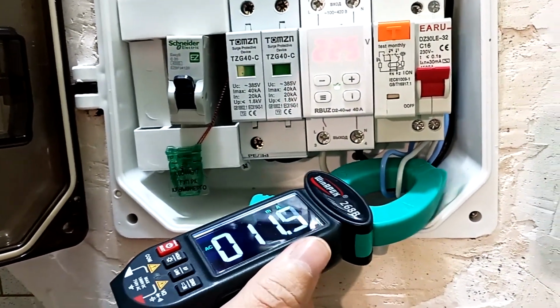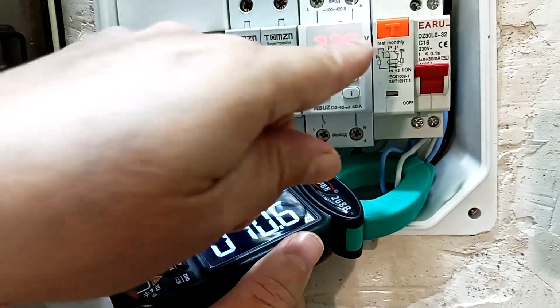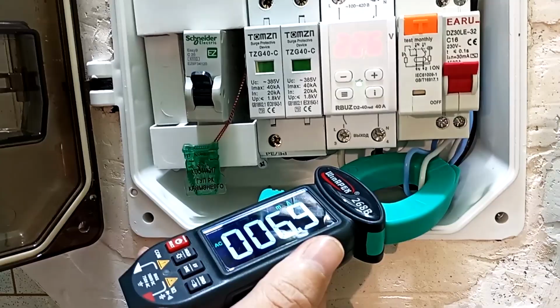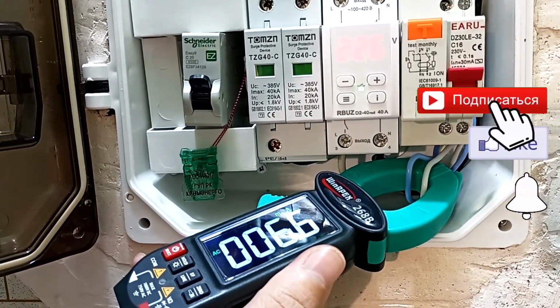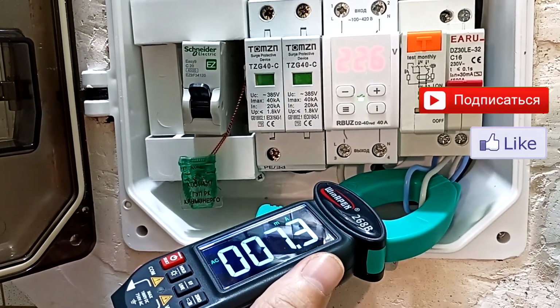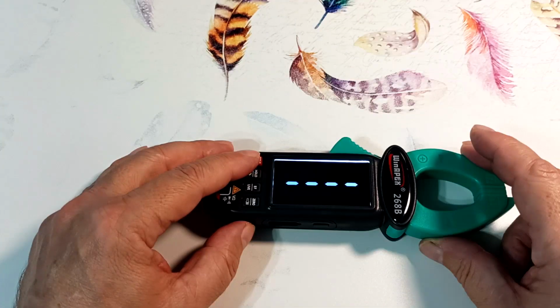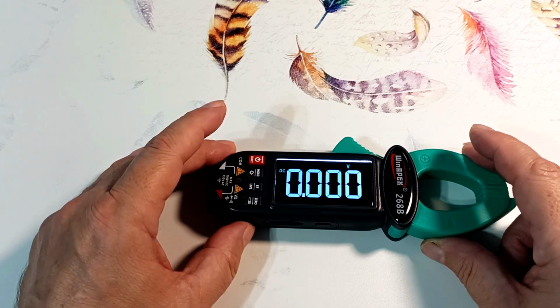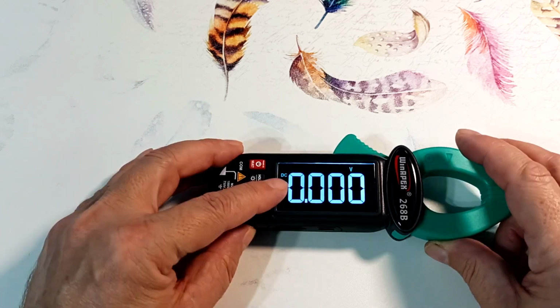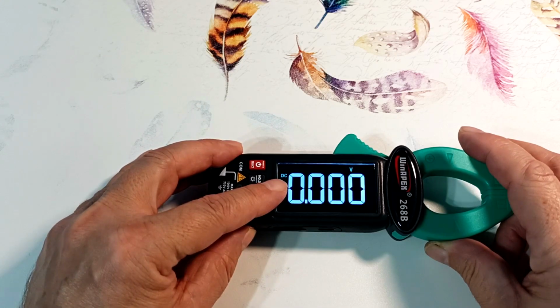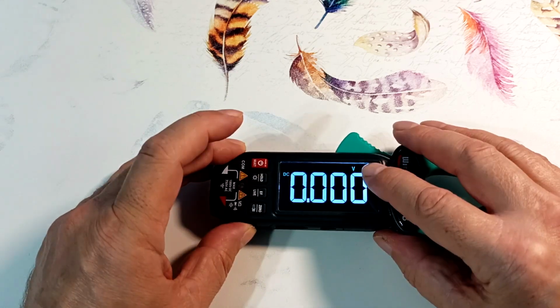If we had a leak of more than 30 milliamp, our automatic circuit breaker would have tripped. Now we have a little less, 7 milliamp. This way we can measure the leakage current in our wiring. Now let's see what other parameters the device can measure. We press the red button, and we switch to the DC voltage measurement mode. This is told to us by the DC icon and the V symbol, which means voltage measurement.